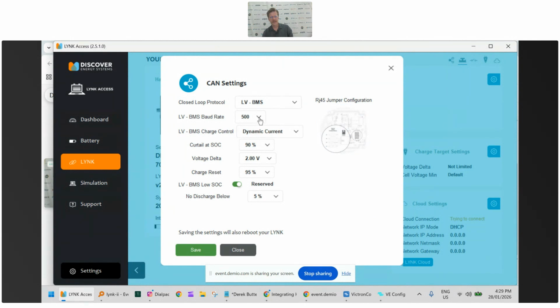The only other thing to take into account is the baud rate. So it might be fixed on the Helios perhaps, but if you do have the option, it's 500 for both Selectronic and Deye or Noark, and for Victron it can be either 500 or 250, but I'd recommend you just keep it on 500, but you do have the option. When you set it up on the Cerbo, when you set up your CAN bus settings, you'll need to set that baud rate as well.